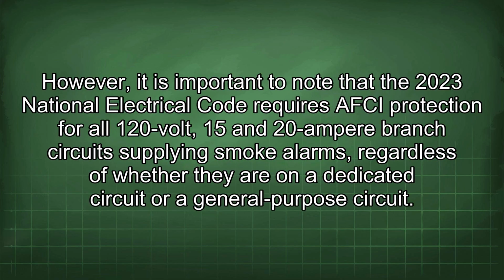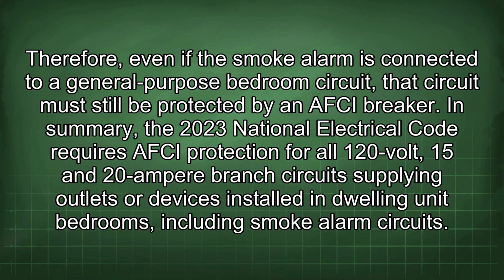However, it is important to note that the 2023 National Electrical Code requires AFCI protection for all 120-volt, 15 and 20 ampere branch circuits supplying smoke alarms, regardless of whether they are on a dedicated circuit or a general-purpose circuit. Therefore, even if the smoke alarm is connected to a general-purpose bedroom circuit, the circuit must still be protected by an AFCI breaker. In summary, the 2023 National Electrical Code requires AFCI protection for all 120-volt, 15 and 20 ampere branch circuits supplying outlets or devices installed in dwelling unit bedrooms, including smoke alarm circuits.